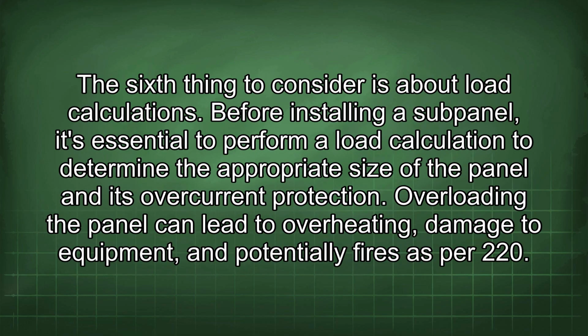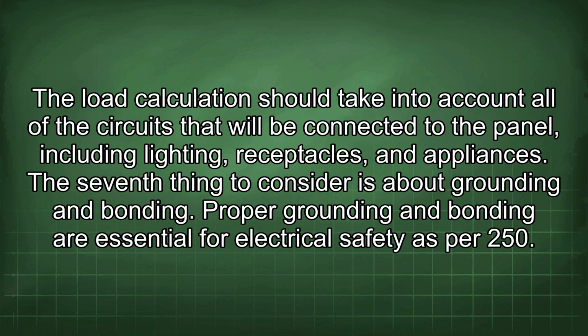The sixth thing to consider is about load calculations. Before installing a subpanel, it's essential to perform a load calculation to determine the appropriate size of the panel and its overcurrent protection. Overloading the panel can lead to overheating, damage to equipment, and potentially fires as per 220. The load calculation should take into account all of the circuits that will be connected to the panel, including lighting, receptacles, and appliances. The seventh thing to consider is about grounding and bonding.